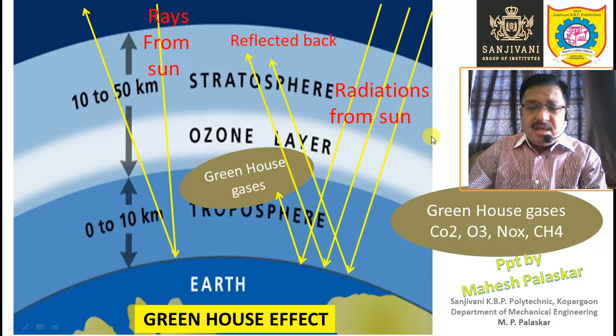Now the global warming potential of some of the refrigerants. We have seen that R11, which is a CFC, has an ozone depletion potential of 1, and the global warming potential is also high, that is 4000. The global warming potential of R12, which is a CFC, is 8500. The global warming potential of R22 is comparatively lower, that is 1500. The global warming potential of R134A is 1300, though its ODP is 0, but GWP is 1300.